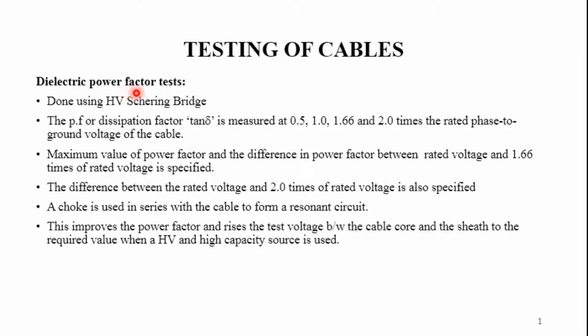Next we have the dielectric power factor test. This dielectric power factor test is done using the high voltage Schering bridge. The power factor or the dissipation factor, tan delta, is measured at 0.5, 1, 1.66 and 2 times the rated phase to ground voltage of the cable. The maximum value of the power factor and the difference in the power factor between the rated voltage and 1.66 times the rated voltage is also specified. Sometimes the difference between the rated voltage and 2 times the rated voltage is also considered.